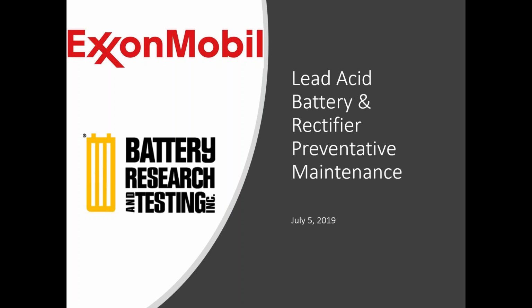Yep, and they really don't require it. Like I said, it's very infrequently that equalization is called for on those batteries. So that's why the stickers have to do with the battery technology that's being deployed. The other thing, with the equalization, I was going to take a step back. It's very infrequently even needed for the lead calcium flooded batteries of today. That was more back in the days of antimony and some of the very early chemistries that did require periodic equalization. So honestly, it's almost something they should take out of a lot of the chargers altogether.